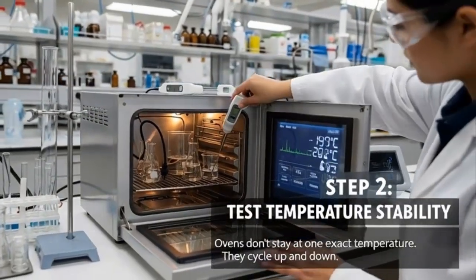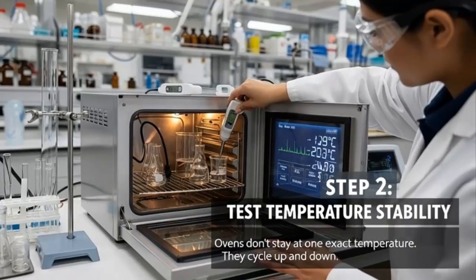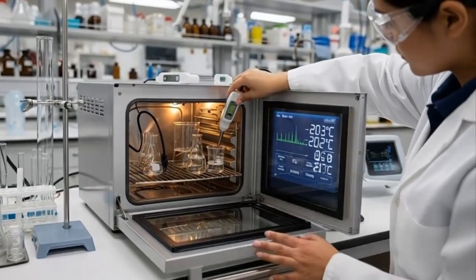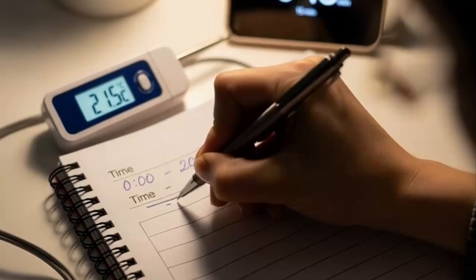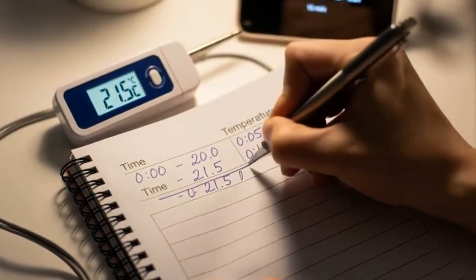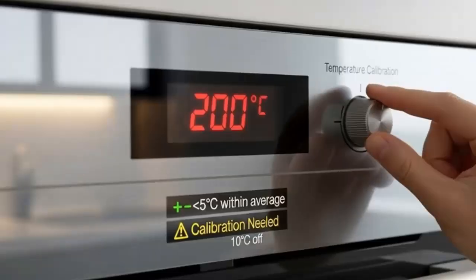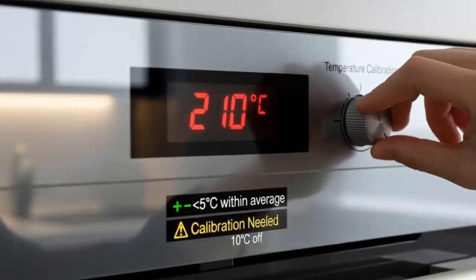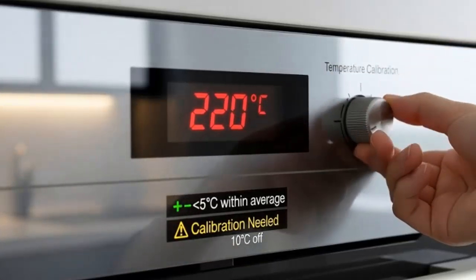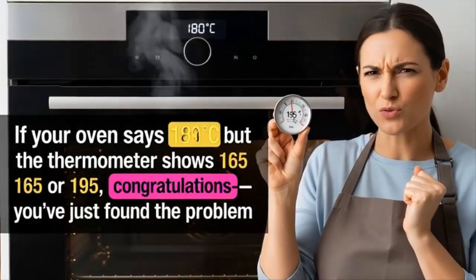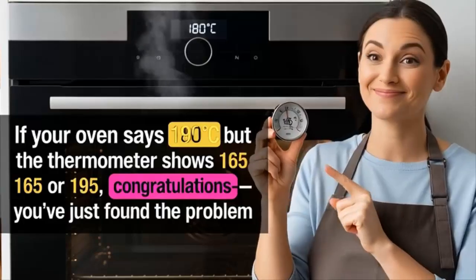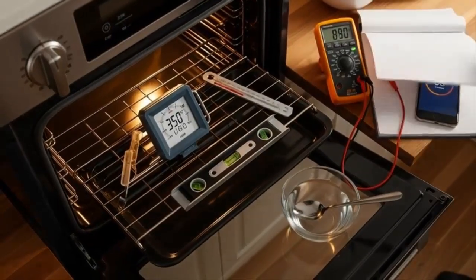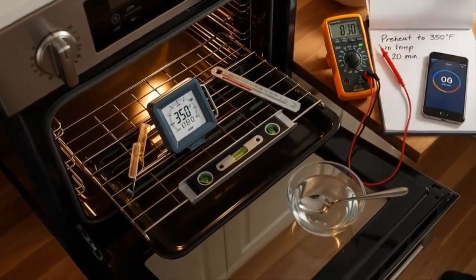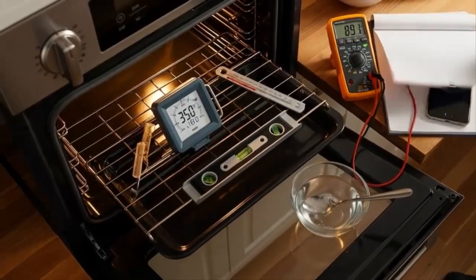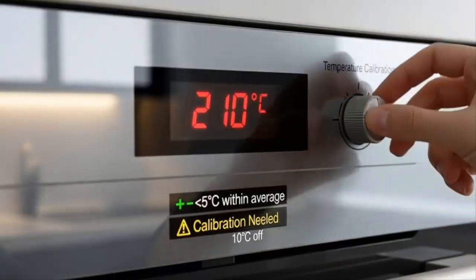Step 2. Test temperature stability. Ovens don't stay at one exact temperature. They cycle up and down. So here's what you do next. Over the next 15 minutes, check the thermometer every 5 minutes and write down the readings. Then calculate the average. If the average is within plus or minus 5 degrees Celsius, your oven is doing fine. If it's off by more than 10 degrees Celsius, calibration is needed. This step is important because some ovens look accurate at first, but drift badly over time.